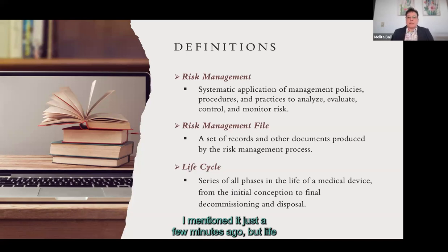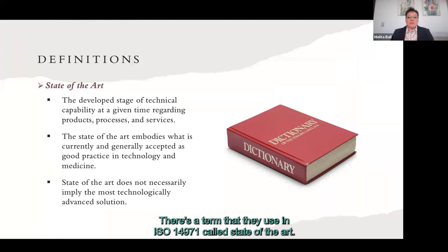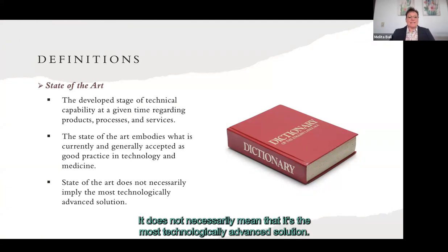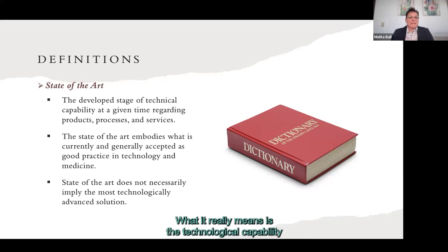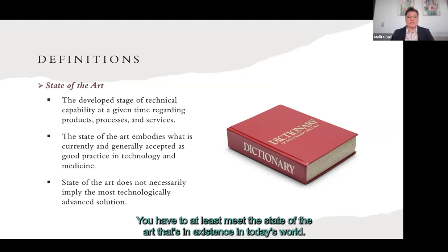The life cycle covers all phases of a medical device from initial conception — even before design control begins — all the way through decommissioning and disposal. There's a term in ISO 14971 called 'state of the art' that many people find confusing. It does not necessarily mean the most technologically advanced solution. It really means the technological capability at a given time regarding processes, products, and services — analogous to the 'standard of care' in clinical settings. It's what is currently and generally accepted as good practice, and your device must be analyzed against that.